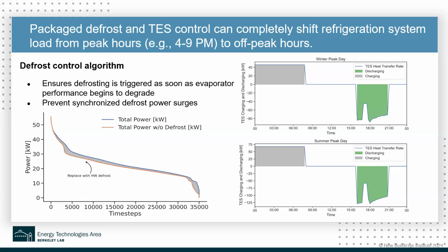On the right side is the performance of the installation of a liquid CO2 storage tank. The upper plot shows the discharge on the peak times from 4 to 9 p.m. And this peak period is the same peak period across the entire year, and the only difference is the mid-peak period. Here we propose to charge for 8 hours during off hours and discharge the cold CO2 refrigerant to switch off the existing compressor and reduce the system demand.